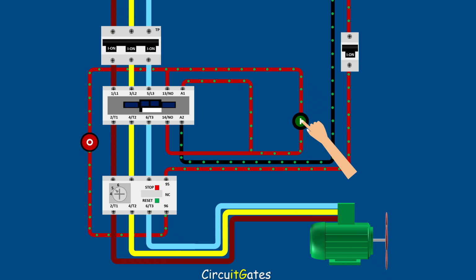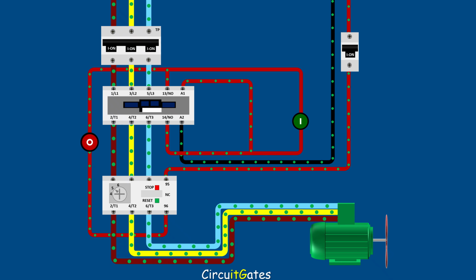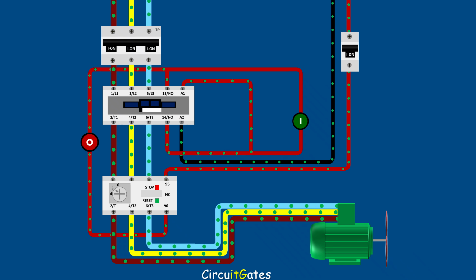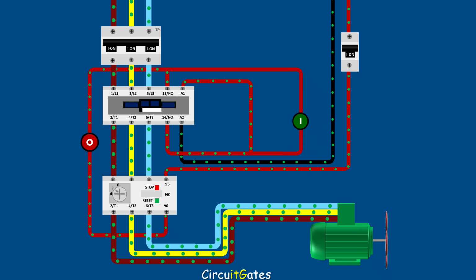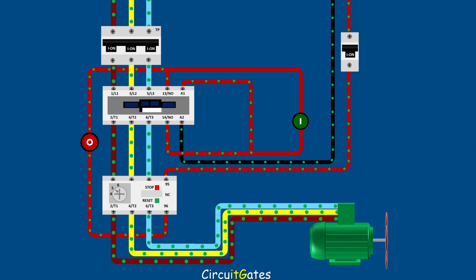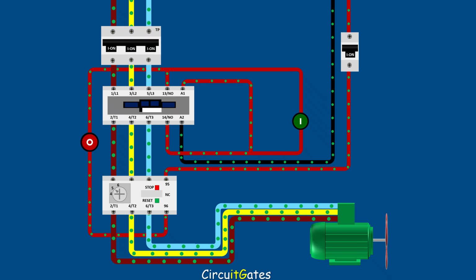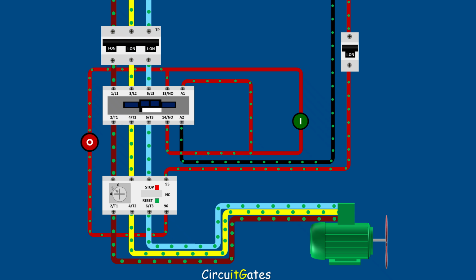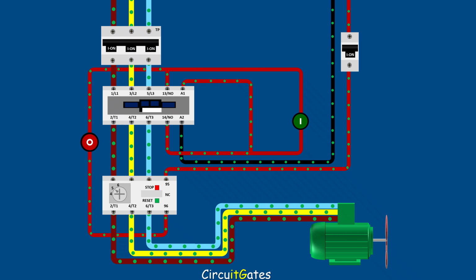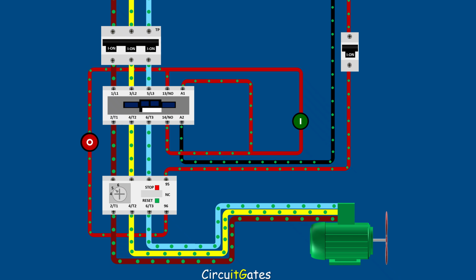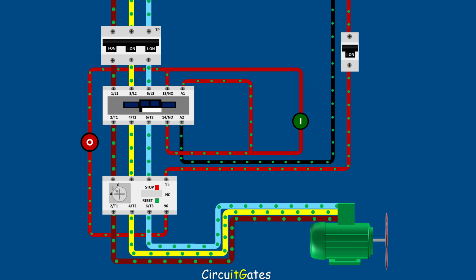The circuit breaker and overload relay on the starter power circuit are used to protect the electric motor from overcurrent conditions. Overcurrent is a condition that exists in an electrical circuit when the normal load current, or current that is supposed to flow in a circuit, is exceeded. Overcurrent can be due to a short circuit or an overload. A short circuit results in flow of very high current in a circuit, and current due to overload may be just above the normal circuit current.